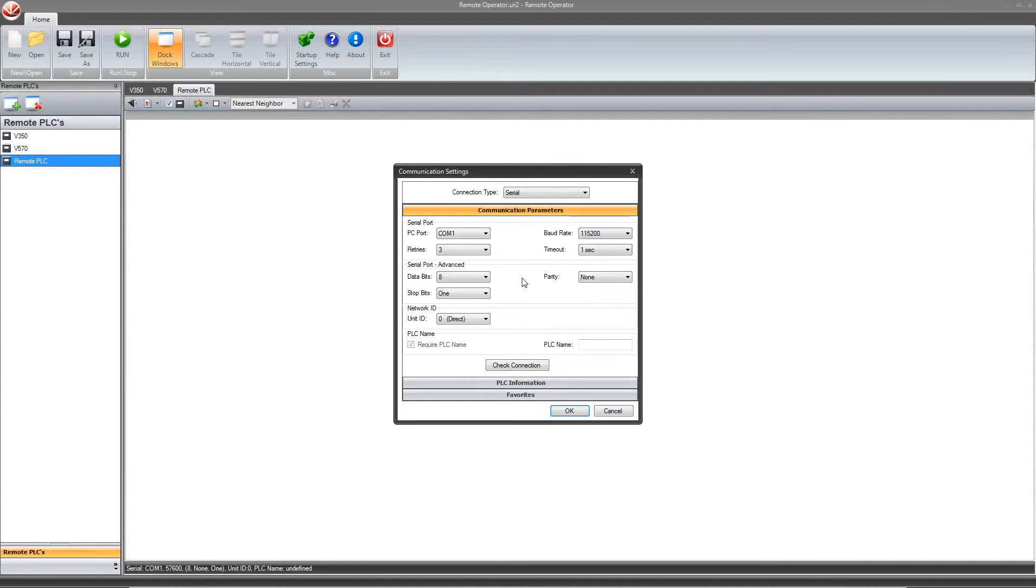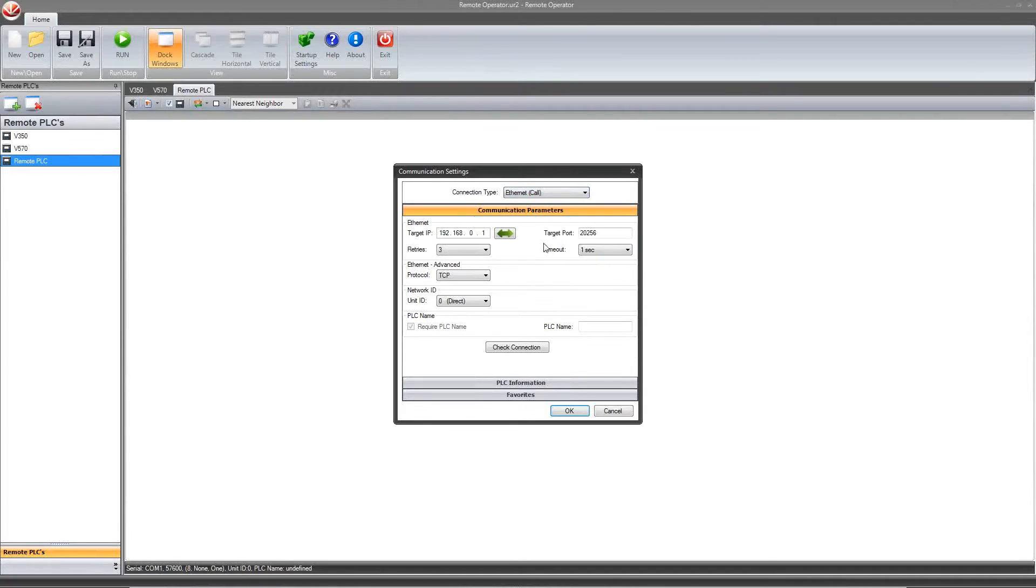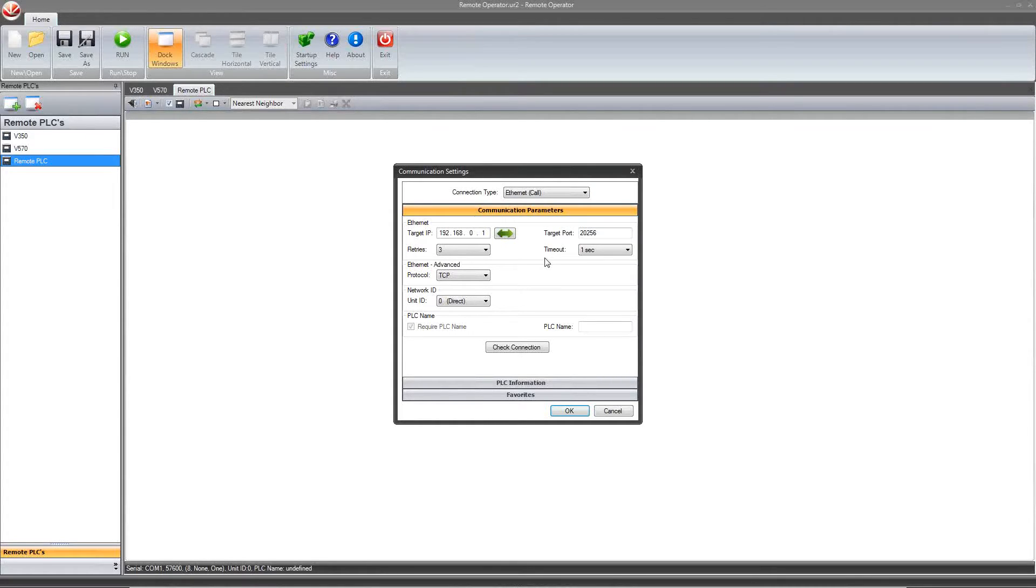You can also choose Ethernet call if you are trying to access the controller through a network. You will need to enter the specific controller's IP address and connect using an open port. Our controllers each have four sockets to communicate through, so make sure to access one that is not in operation. If multiple PCs are connecting at the same time via Ethernet, please ensure that each is connecting to a different available socket.